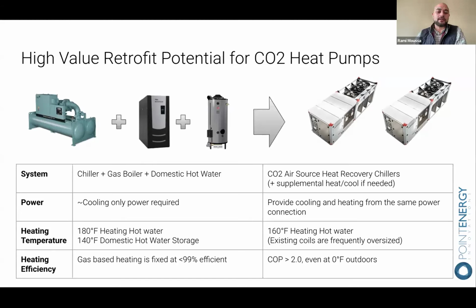We can actually fit all of those services into a single power connection that ideally would also fit within the existing chiller capacity or connected load. So we have the ability to retrofit this equipment within existing power infrastructure. For conventional heating operating ranges where we may see 180 degree, 160 degree heating hot water, that CO₂ heat pump can do that. It can provide that higher grade heat and avoid costly upgrades to heating coils within the building that would be required for lower temperature, more conventional heat pump technology.